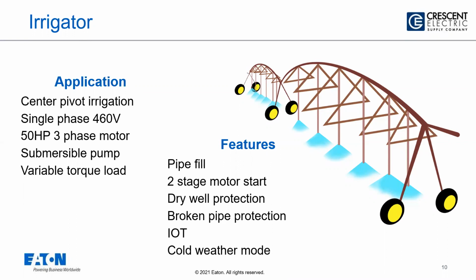Again, I'm going to talk to you about 2 applications, one for a variable torque, for an irrigator application, and the next one will be a constant torque. And this one is a center pivot irrigation system where the single phase can be either, here it is a 460, but don't feel if your motor is 230, we can still work with it, derate our drives and get it to you for a 3-phase motor application. And in this case, it is a submersible pump. We have configured it as a variable torque load application for this pump application.